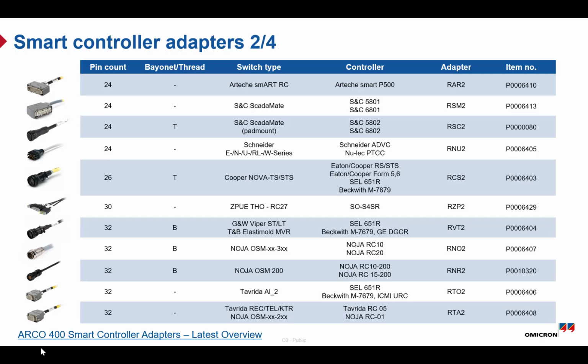Safety is also a key feature. All connections, including the test set extension cable and the adapters, are designed to be touch safe with no exposed pins. In addition, the software continuously monitors the setup. It can detect issues like missing ground connections and will warn you if live currents or voltage are active. From a usability point of view, the software makes it easy to start testing quickly. You simply select the controller relay type and begin your test. No complicated setup required. You also have different extension cable options, allowing you to work comfortably whether the controller is closed or mounted at a height.